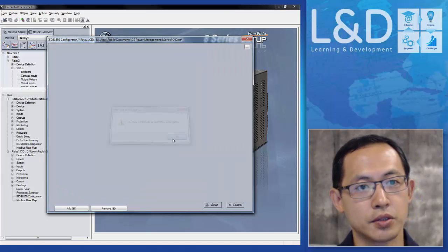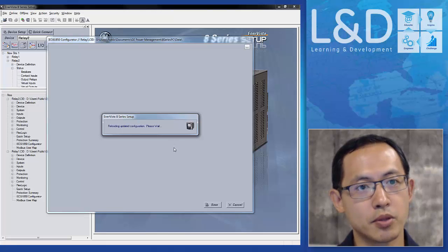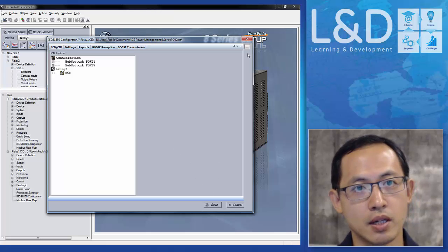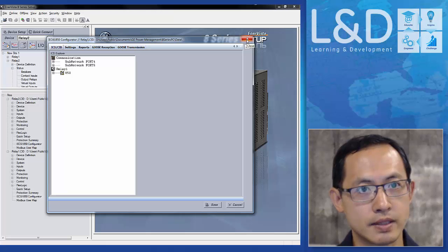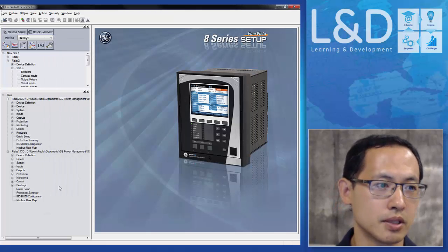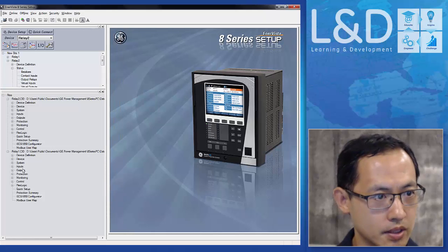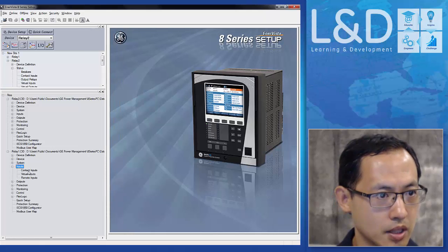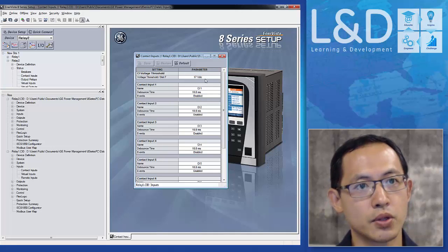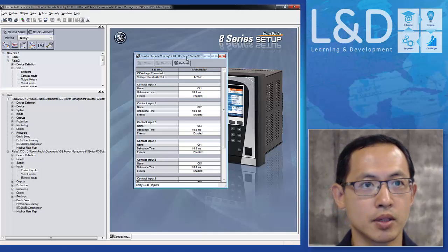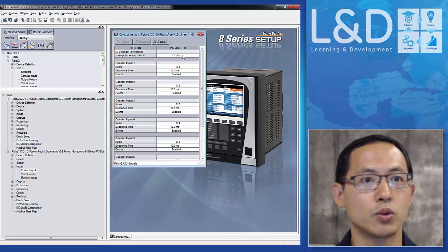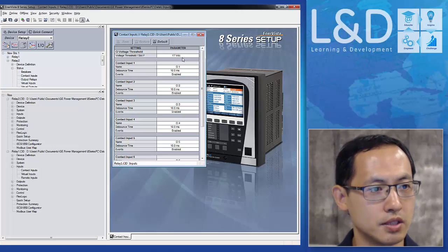After that, in order to make the relay 1 publish the GOOSE message of the phase IOC pickup and the contact input, I have to check the relevant settings about the contact input and the relay IOC pickup. So first is the contact input. I want to make sure that the threshold is 17 because I'm using RTT, which can output only 24 volt DC.